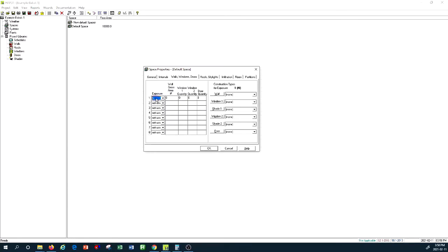Remember that when you select any exposure orientation or direction, you input all of your surface area for that wall in square feet, because this is set for imperial units. You also input the quantity of windows in that space for the north orientation. We'll get to windows in a second, but here you input the quantity of your windows that you've already defined. If you have multiple types of windows that are not the same size or don't have the same properties, you may want to use Window Type 2.